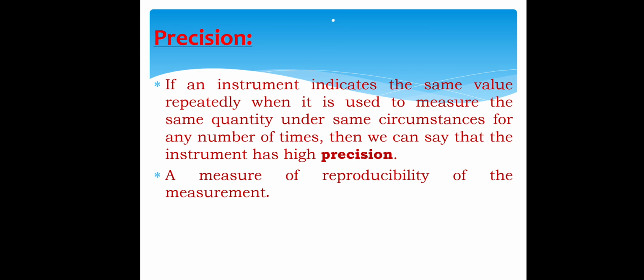The second one is precision. Precision means the instrument indicates the same value repeatedly when it is used to measure the same quantity under the same circumstances any number of times. Then we can say that the instrument has high precision. For example, the first time I measure the temperature I get 26.1, the second time 26.1, the third time 26.1. Any number of times I measure, I get the same value.